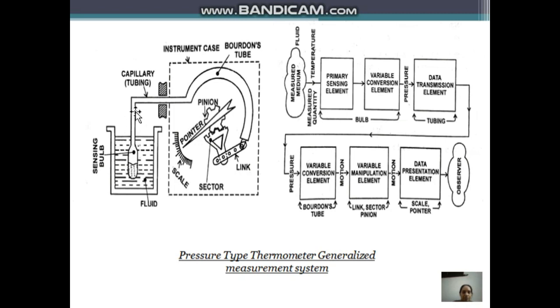The capillary tube carries this mercury to the Bourdon tube. By the rising of the mercury, the Bourdon tube expands. Due to the expansion of the Bourdon tube, this link moves, which makes the sector move. This sector moves the pinion, and the pointer moves along the temperature calibrated scale. Then you get the output.